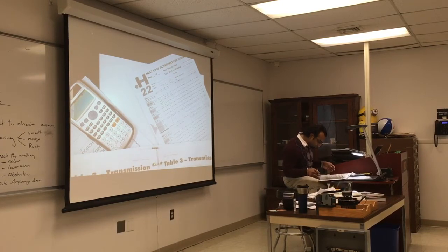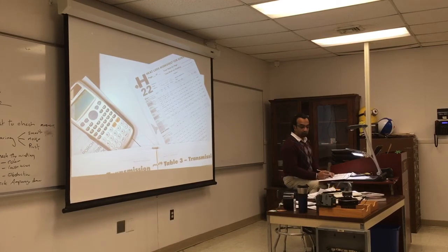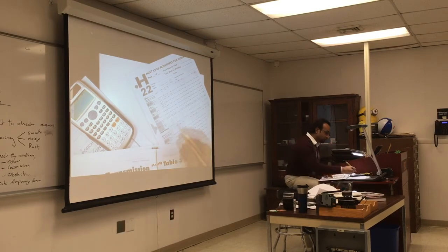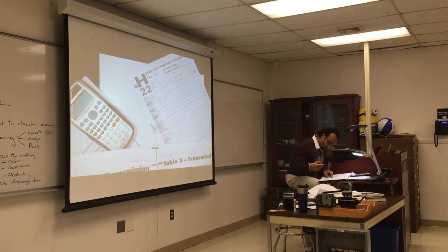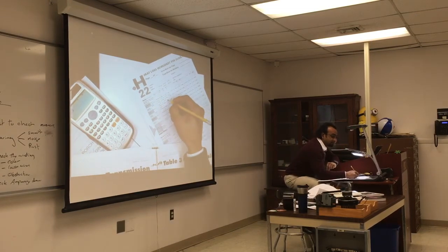Oh, ceiling. Frame wall. Ceiling, here. So we're back with attic space above. Here you go, table 3, section 22, ceiling with attic above. So I'm going to pick this one, and you put that in here. The ceiling is going to be the same for all rooms, right? You're not going to change ceiling in every room. You just pick the type of ceiling for the entire house. So I'm going to pick F, which is 0.070, and put that here.